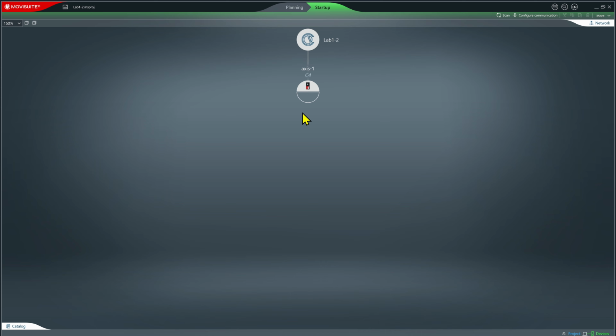So following the instructions, I make sure that my demo unit's DI00 switch is off. That inhibits my drive. That's a smart thing to do because you wouldn't want the motor to accidentally move during commissioning. In a real-world application, that could be very dangerous. So we disable the drive.